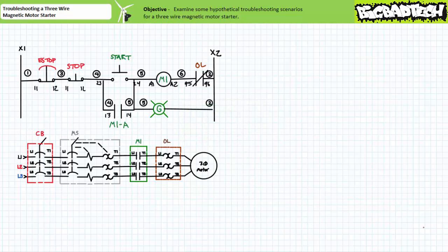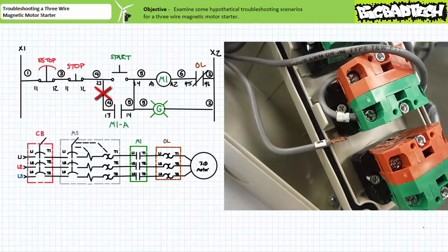Most likely, the source of the lost holding contact problem is an open wire. Very often, a visual inspection will quickly reveal the wire at fault. Most likely, the wire was inserted into the proper terminal. However, it wasn't fully secured and came out when the push button station was closed. Systems having undergone some form of unexpected movement or cumulative vibration might exhibit this sudden loss of functionality.